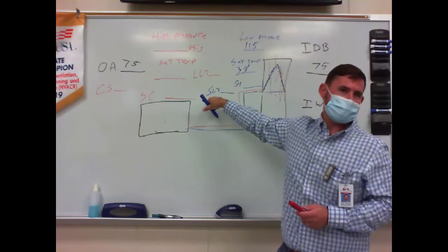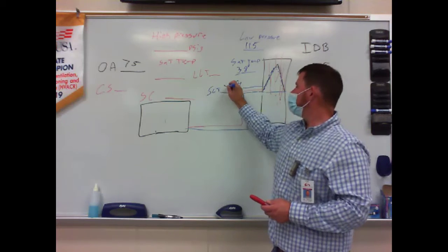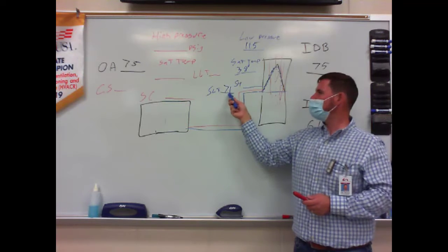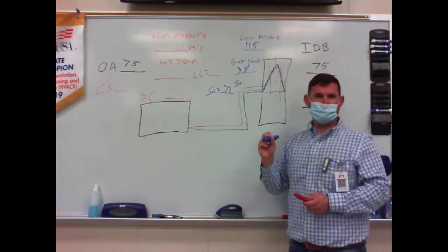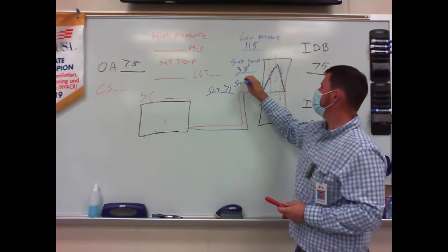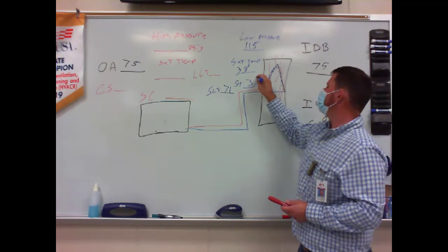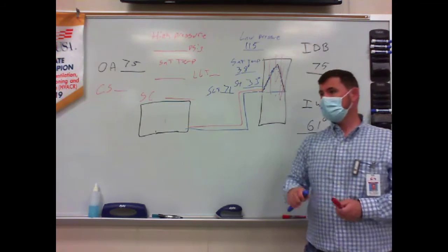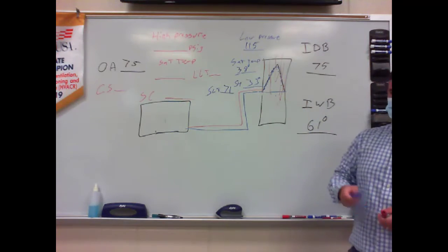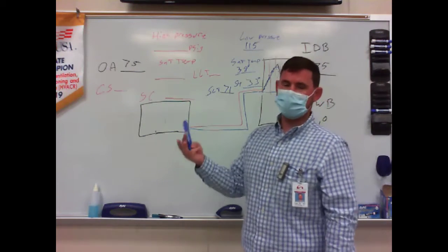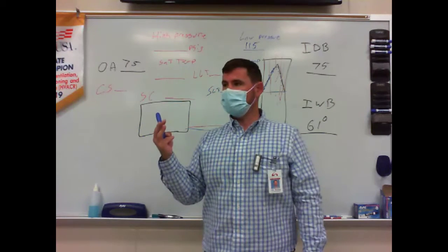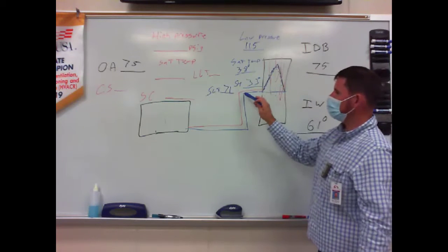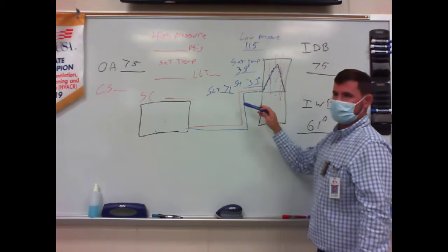What was my suction line temperature? 71. So how much superheat did I have? How much heat did I pick up past my saturation? About 33 degrees. Is that a lot of superheat? Yeah. So what do I know about my evaporator now? Is it flooded? Is it starved? Or is it normal? Starved. Flooded would be too much refrigerant in it, right? If I had too much refrigerant, I'd be leaving at the same temperature I'm saturating at.